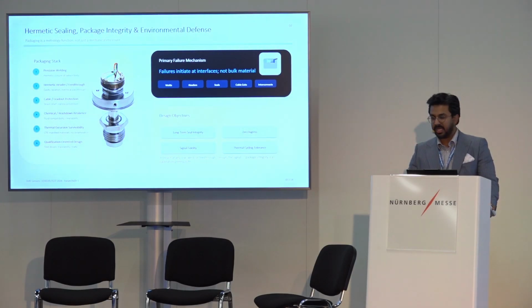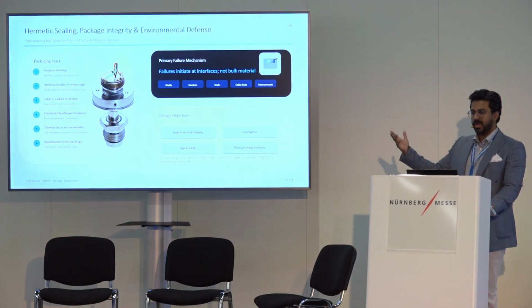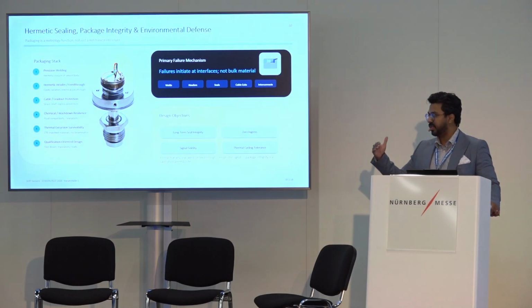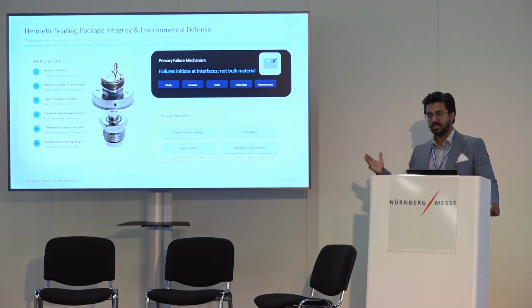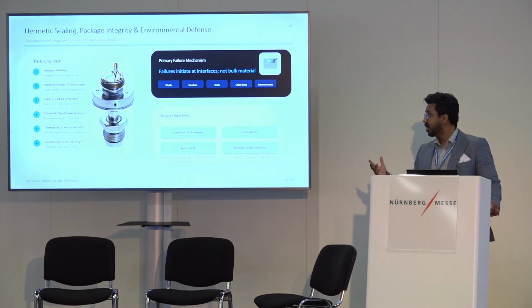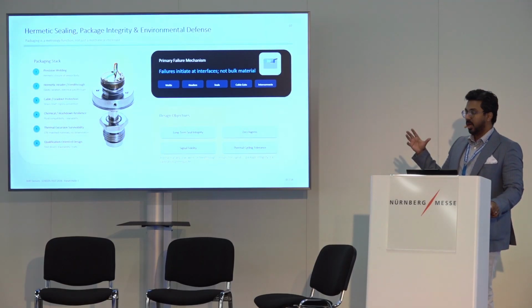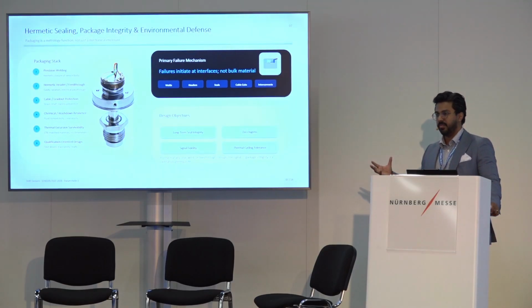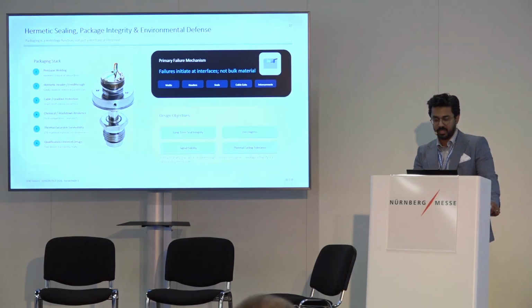So there are different transitions happening within the package, and within every transition, other than the sensor element itself, we have to create variability and test parameters and qualifications, so we can understand and put it into the design aspect when designing these high-pressure, high-temperature applications, even before calibration comes into play.